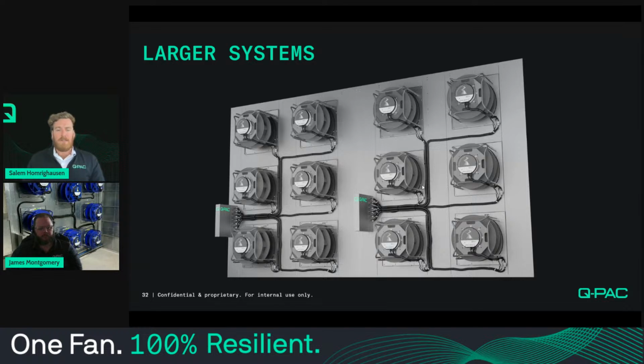Another thing is the multimotor plenum fan will go from 5,000 to 90,000 CFM. You can think of the product as an array of multimotor plenum fans, but with a more intuitive sense to it, where you're able to use multiple MPFs together easily. So you can go all the way up to 230, 250,000 CFM, or higher. It really depends on the scale of the project and how many ECM plug fans and MPFs you need. As a starting point, if your project exceeds 250,000 CFM, or exceeds 90,000 CFM for a single unit, that's something you'll want to work directly with Q-PAC on. As the scale of the job and performance range increases, reach out to our team. But it is possible for any CFM, as long as the static pressure is between 1 and 9 inches.